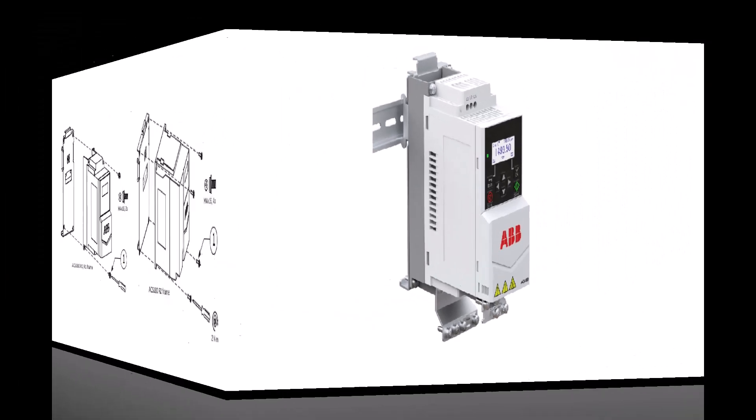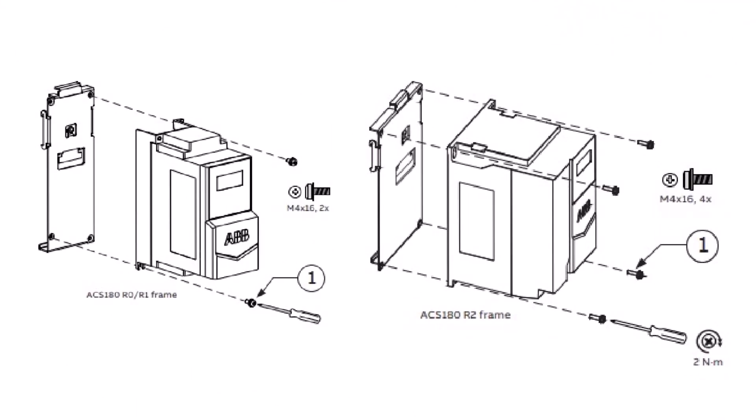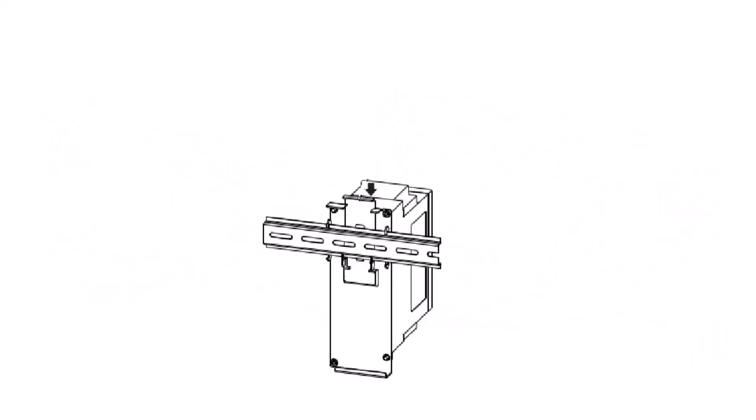For frames R0 to R2, an optional BDRK-01 or BDRK-02 DIN rail kit is required for DIN rail mounting. Align the mounting holes on the DIN rail kit to the back of the drive before installing the hardware. Next, connect the top portion of the DIN rail kit to the DIN rail.